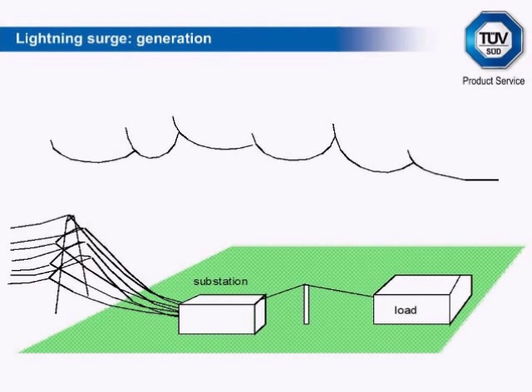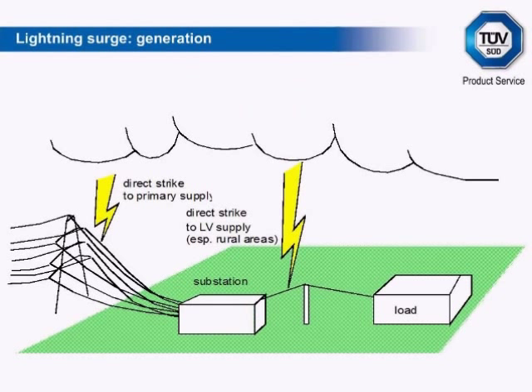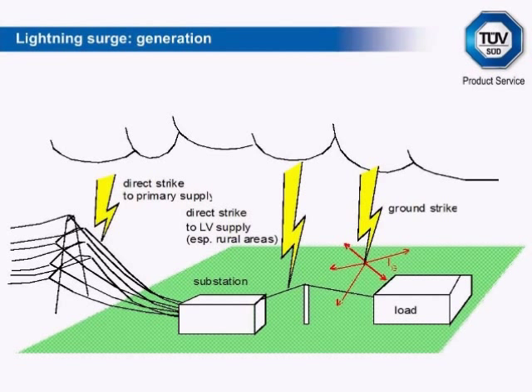The surge test applies high-energy but relatively low-bandwidth transients, particularly representing those attributable to nearby lightning strikes. Lightning can couple to power and other external lines in three generic ways: direct, by a strike to an overhead or exposed line; indirect, via ground coupling, where lightning strikes the ground causing a transient potential gradient applied to ground-referenced cables; or indirect from cloud-to-cloud strikes, where magnetic and electric fields induce surges in cables on or near the ground.